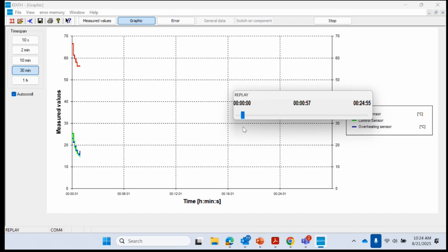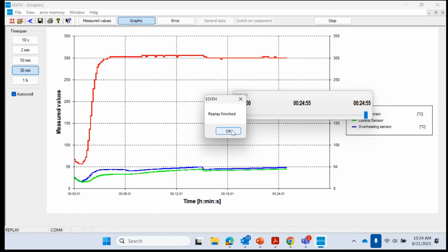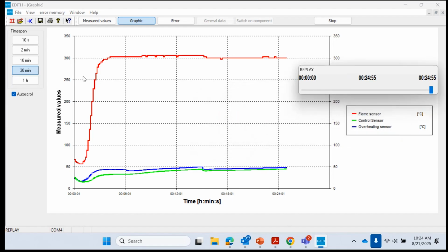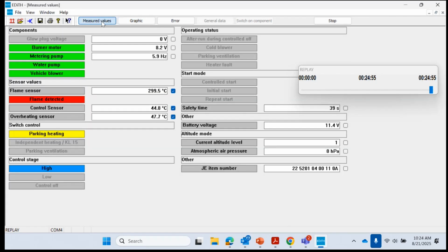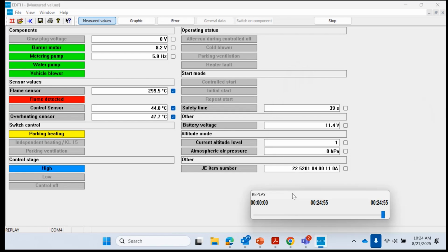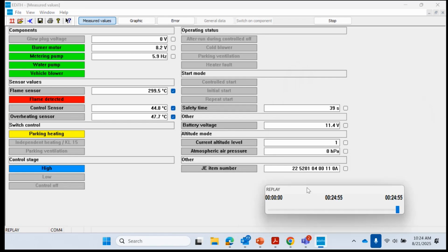Because this is a recorded version, I can just scrub the timeline all the way towards the end. It's a 24-minute file, and now you can see the entire graph from start to finish of the testing of the heater. So you are able to visually see the graph, or you can read out the measured values. This helps you check the operation of the heater and compare it with good known values. It also shows you the battery voltages measured at the heater. So very useful tool.